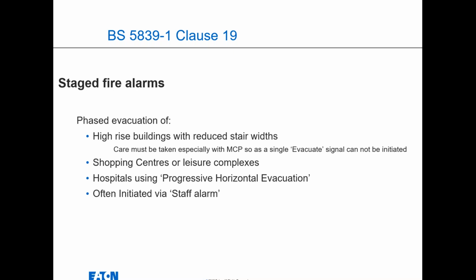Again, in some of the larger projects that you may come across, there are staged fire alarm systems. That's phased evacuation: high level buildings, shopping centres, generally where there are a lot of people involved. Therefore, you can't just tip everybody out of the building at the same time because you'll get bottlenecks and stampedes. Hospitals generally use a progressive horizontal evacuation, patients moving sideways, until the fire brigade may have to take them completely out unless they get it under control. So there are different staged alarm systems and cause and effect, as they call it, for different building types, and you just need to consider that when you're doing it.